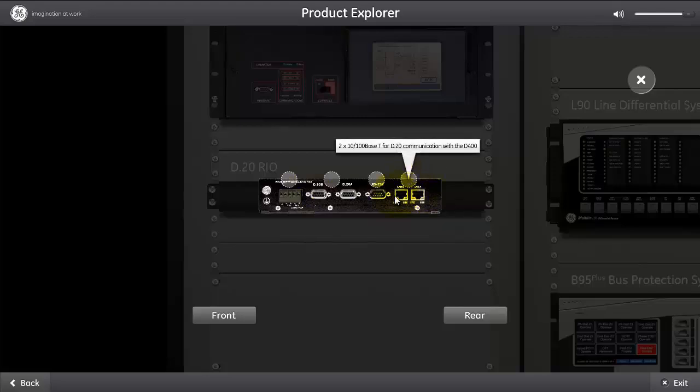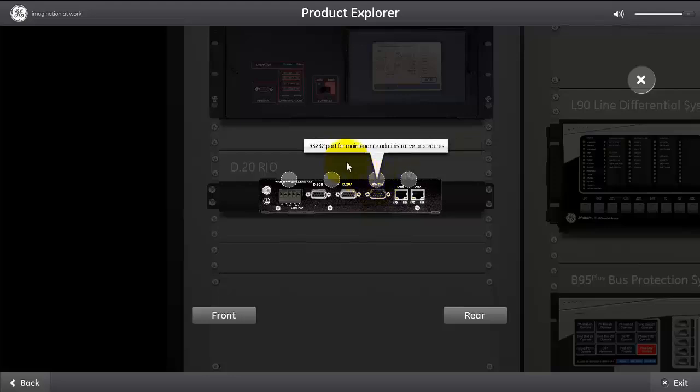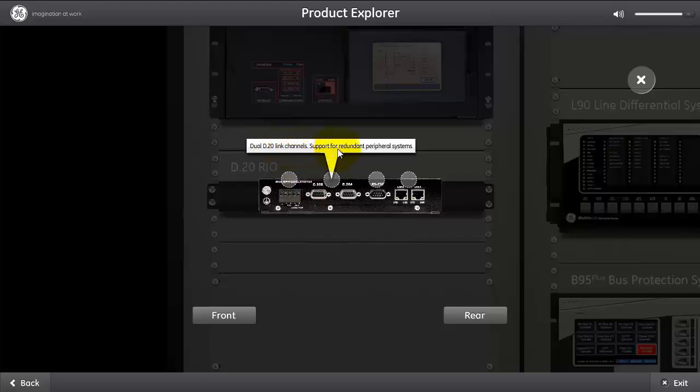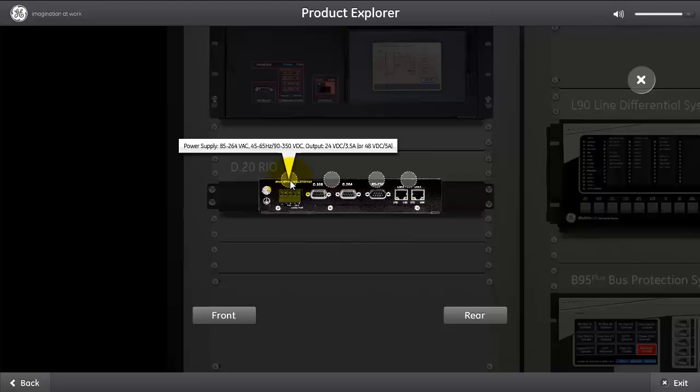From the rear of the Rio, we've got the 10/100 base for D20 communication with the D400. We've got the RS-232 maintenance port, and this is to set up the IP address of the Rio. We've got the two D20 link channels that support redundant peripheral system connections to the Rio. We also have the power supply, which could be 85 to 264 volt AC, 45 to 65 hertz, or 90 to 350 volt DC output with 24 volt DC 3.5 amps, or 48 volt DC at 5 amps.